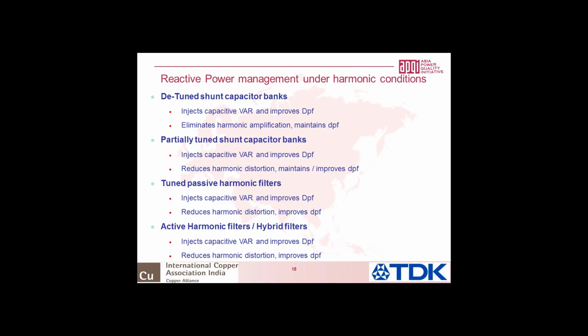Then we have, in the next category, tuned passive harmonic filters, which not only inject fundamental capacitive VAR and improve displacement power factor, they can actually reduce harmonic distortion and improve distortion power factor, which means they can actually improve the true power factor. Then the last of the league is active harmonic filters and hybrid filters. Hybrid filters are active filters plus a combination of detuned capacitor banks or passive filters. They inject capacitive VAR and thus improve the displacement power factor. They also reduce harmonic distortion and improve the distortion power factor, which means they can improve the true power factor.